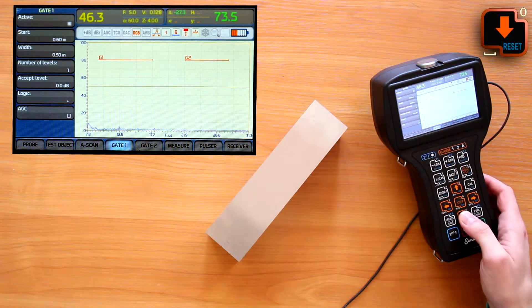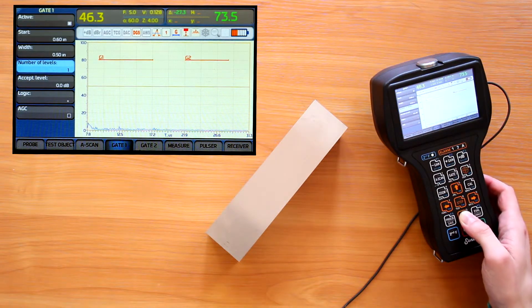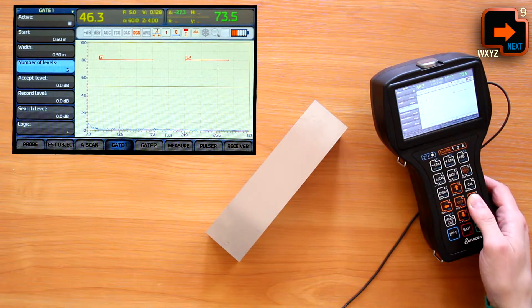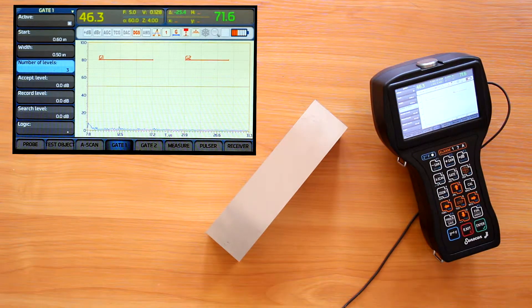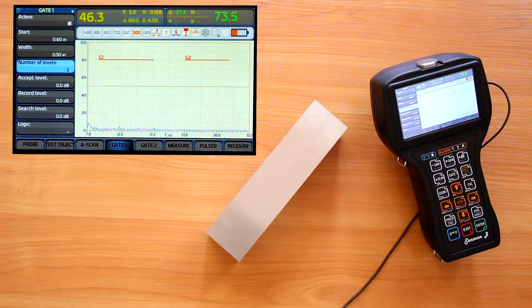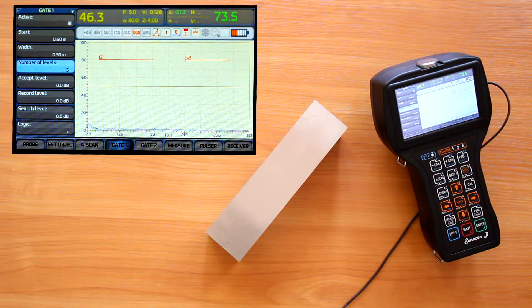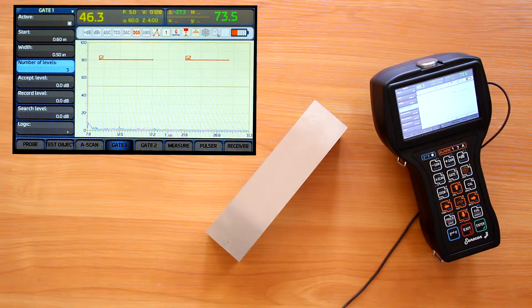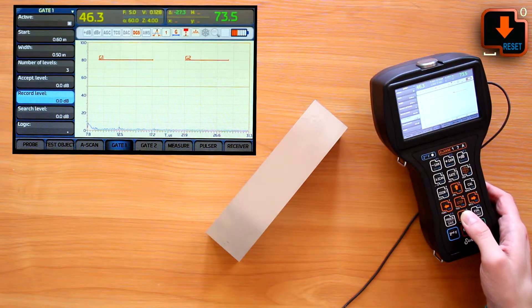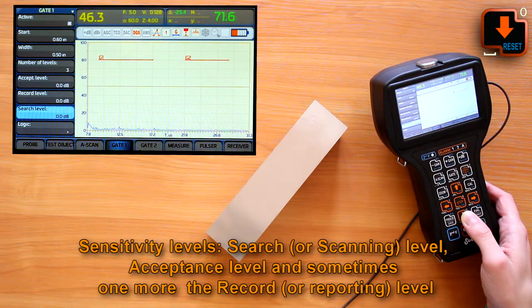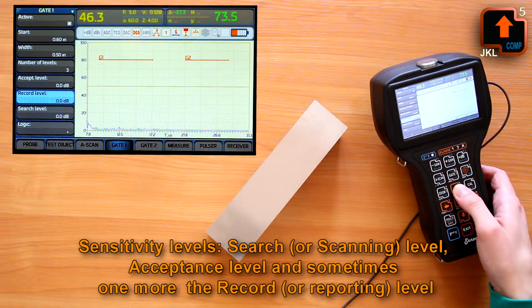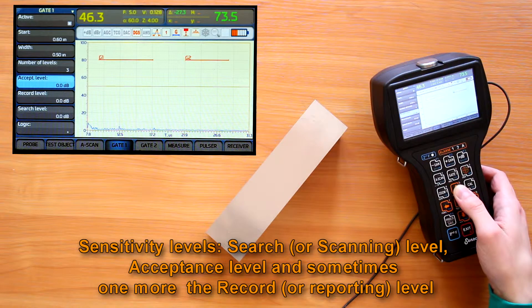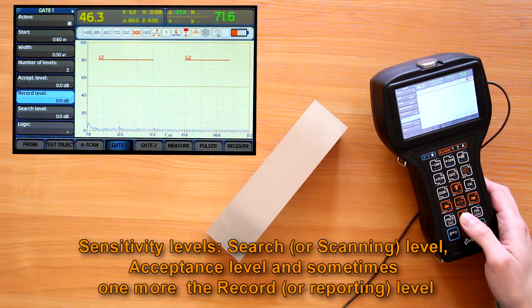Here we can set the number of levels from 1 to 3 and positions of each level. Why do we need those extra levels? Let's remind ourselves that according to many UT codes, we have 2 or 3 sensitivity levels. Search or scanning and acceptance level. And sometimes one more, the record or reporting level.